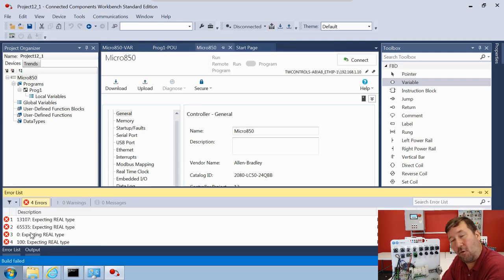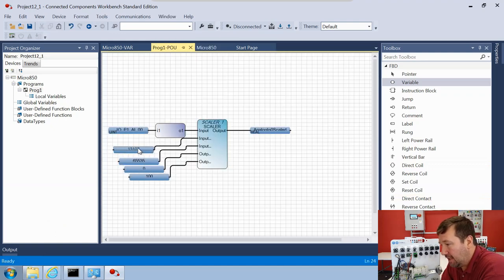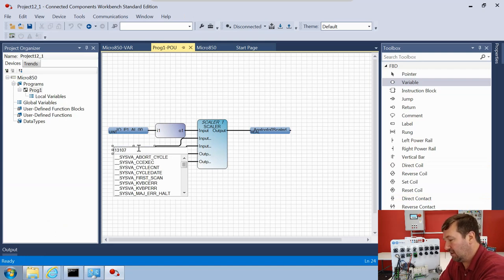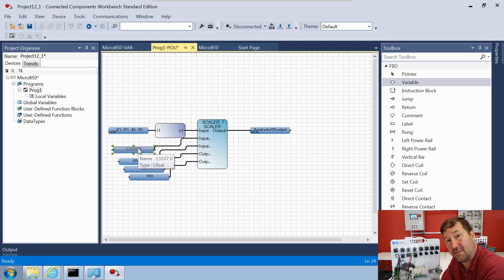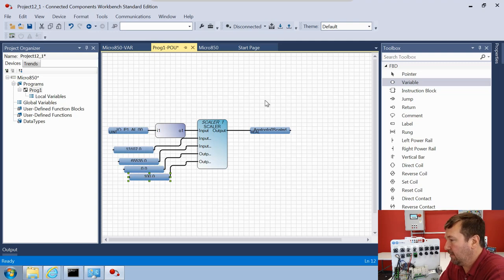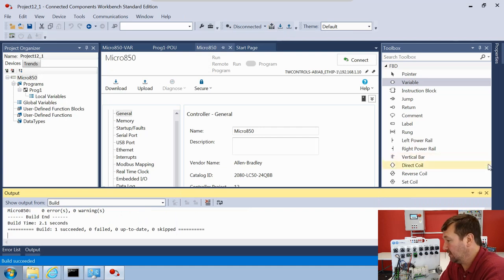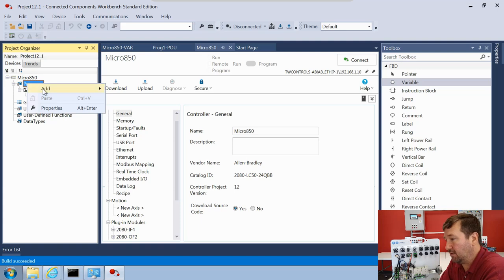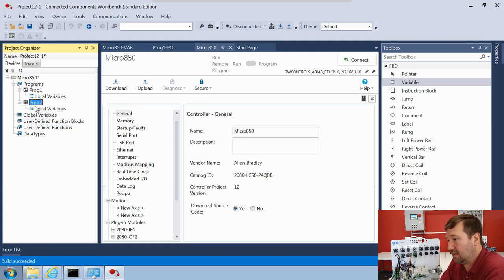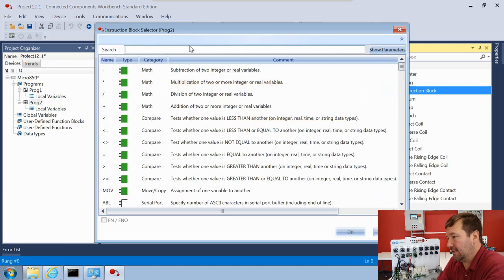Hit the Build button and down here you'll see those integer numbers flagged as 'expecting REAL type'. To fix that, go back and edit 13,107 to 13107.0 — adding the decimal point makes it interpret as a REAL number. Do the same for 65535.0, 0.0, and 100.0. Hit Build again and it compiles just fine. Now let's do the second channel in a Ladder program — add a Ladder program, open it up, bring in an instruction block, and type 'SC' to find the Scale instruction.